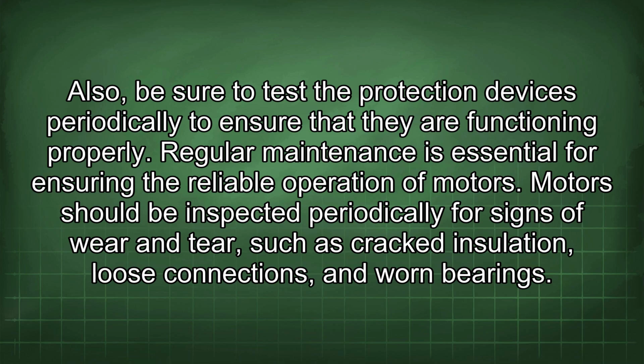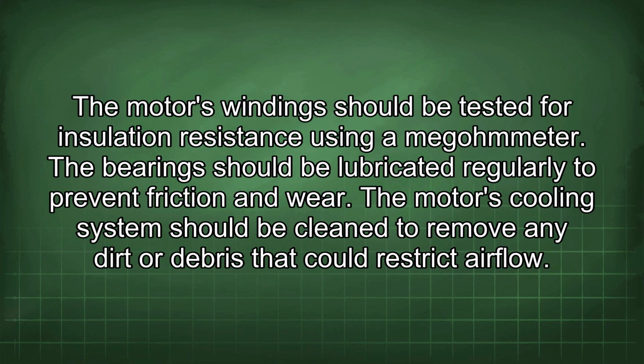Regular maintenance is essential for ensuring the reliable operation of motors. Motors should be inspected periodically for signs of wear and tear, such as cracked insulation, loose connections, and worn bearings. The motor's windings should be tested for insulation resistance using a megohmmeter. The bearings should be lubricated regularly to prevent friction and wear.